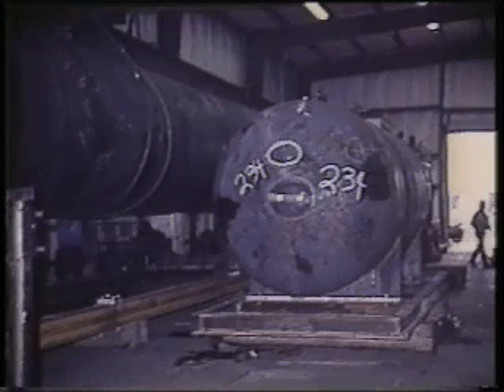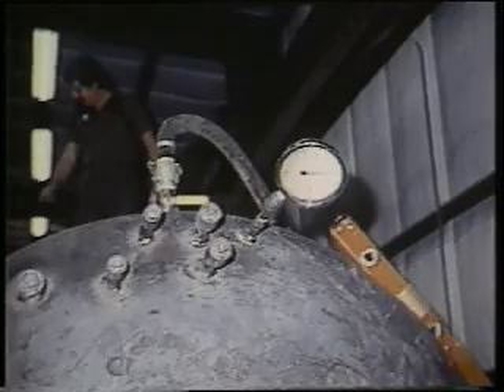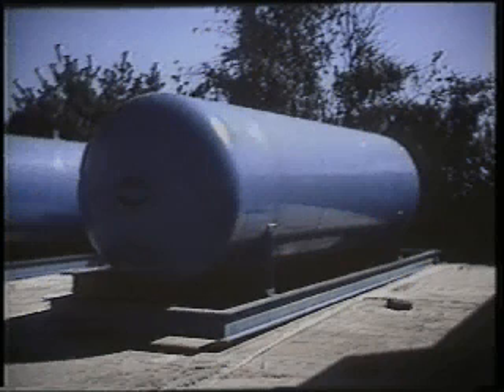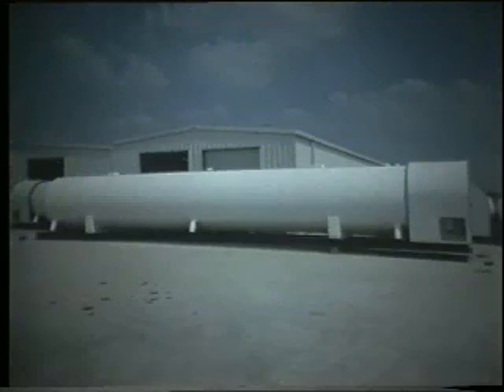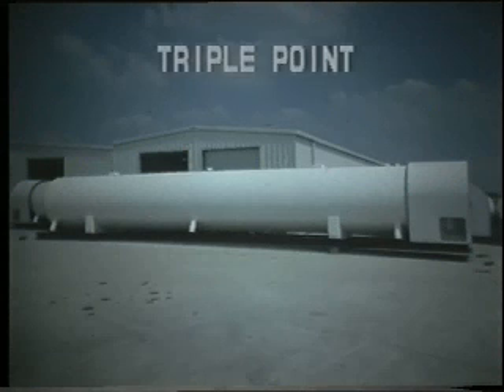When confined within a suitable pressure vessel, carbon dioxide can exist in any of three states of matter: solid, liquid, or gas, depending on conditions of temperature and pressure. The point at which all three states may exist is minus 69.9 degrees Fahrenheit and 60.4 psig. This condition is referred to as the triple point.